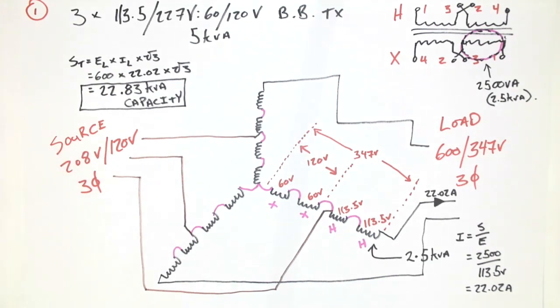So we've got 3 transformers. The total isolation rating would be equivalent to approximately 15 kVA. However, when we connect it as an auto transformer, we get a total kVA capacity of 22.83. Let's take a look at another example.